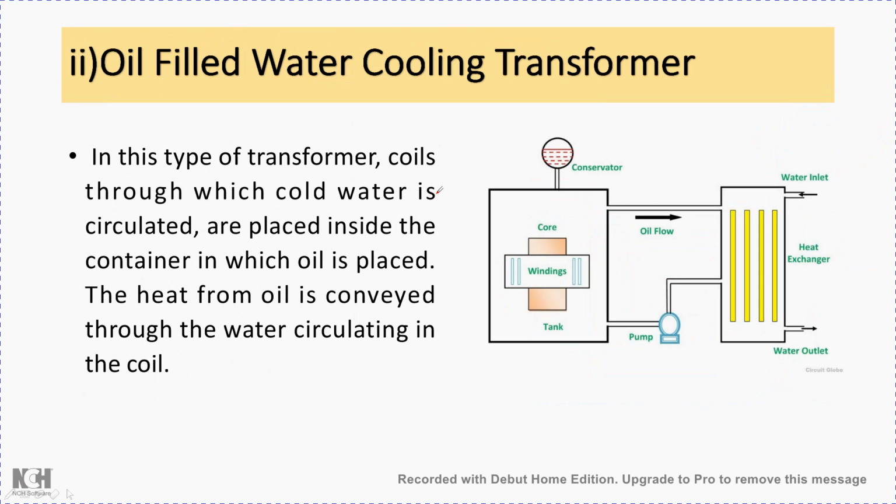And the next type is oil filled water cooling transformer. Here oil will be filled as it is in the tank, and this oil will go to the other cover. This cover will contain water. When the oil passes through the tubes within the water, it is going to get cooled, and this oil will be pumped back into the tank. So oil will stay in the tubes and it will be pumped back later for filling up again in the tank. In this way the oil is continuously cooled.